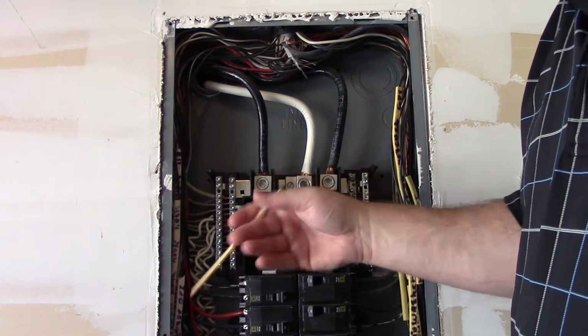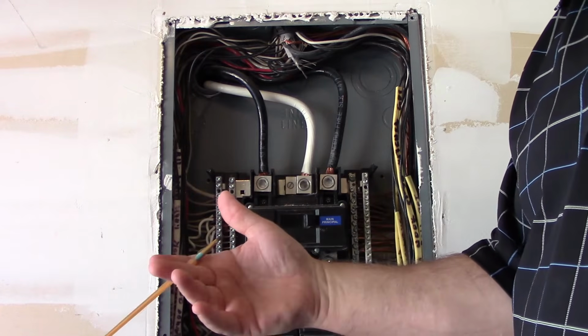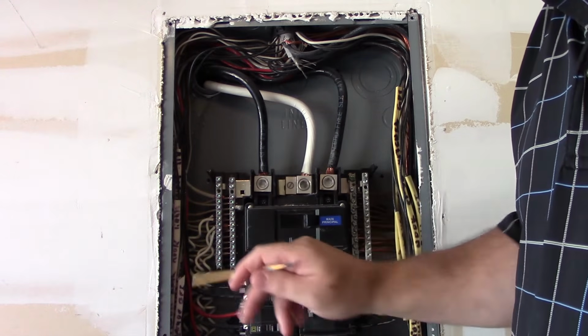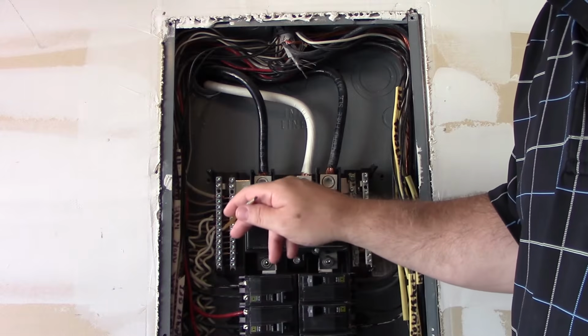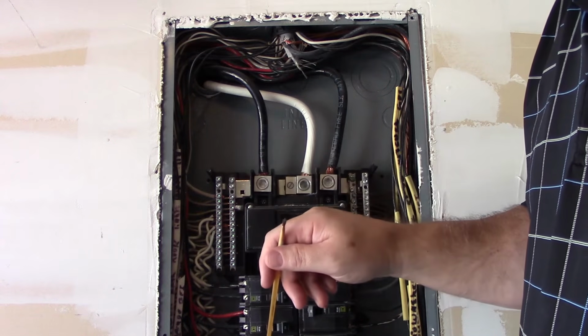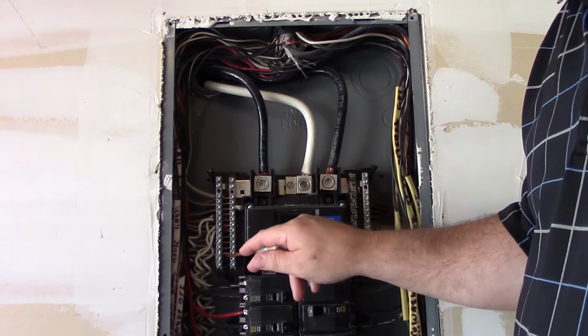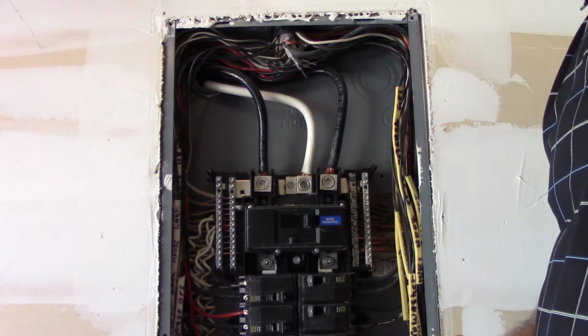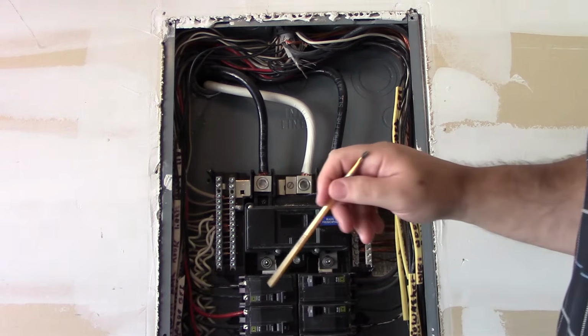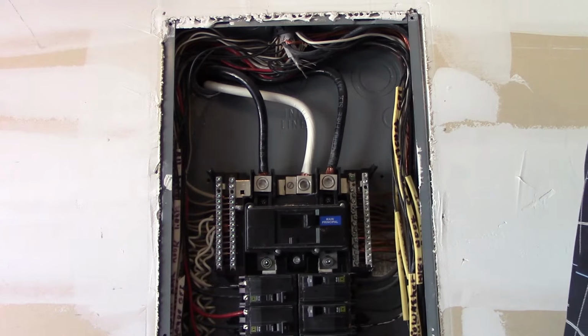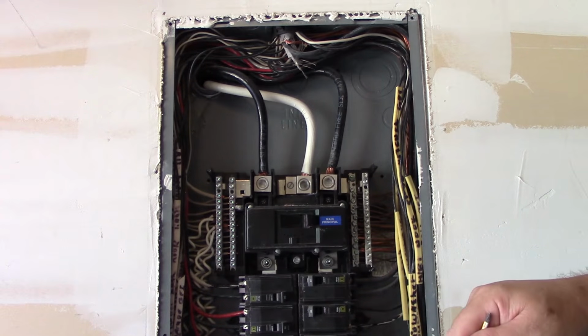It could cause the insulation to overheat, melt down, or deform, and you want to notice any of those things. So look for any arcing, any deformation of the insulation, anything that looks out of the normal, anything that starts to look blackened or what have you. You want to call it out, and you have to do a little more investigation to see why that might be the case.